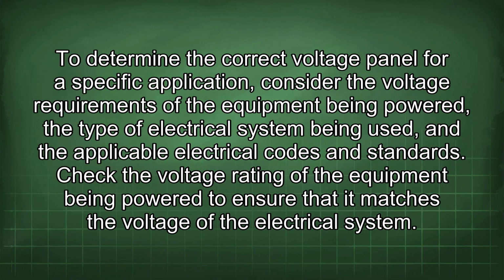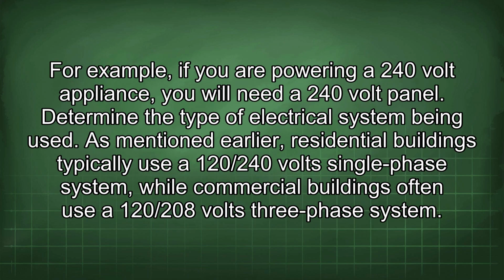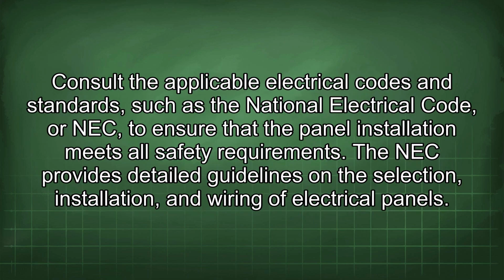To determine the correct voltage panel for a specific application, consider the voltage requirements of the equipment being powered, the type of electrical system being used, and the applicable electrical codes and standards. Check the voltage rating of the equipment being powered to ensure that it matches the voltage of the electrical system. For example, if you are powering a 240-volt appliance, you will need a 240-volt panel. Determine the type of electrical system being used. As mentioned earlier, residential buildings typically use a 120/240 volt single-phase system, while commercial buildings often use a 120/208 volts three-phase system. Consult the applicable electrical codes and standards, such as the National Electrical Code, or NEC, to ensure that the panel installation meets all safety requirements. The NEC provides detailed guidelines on the selection, installation, and wiring of electrical panels.